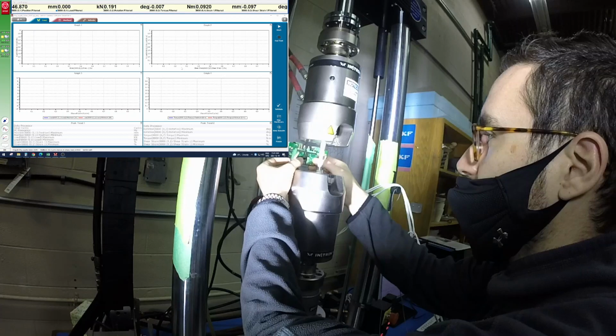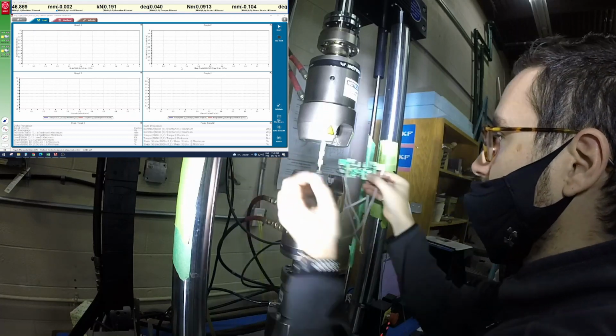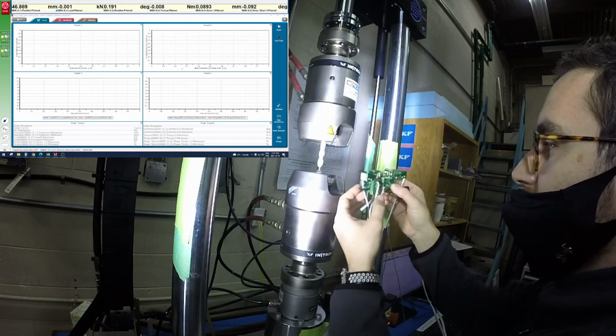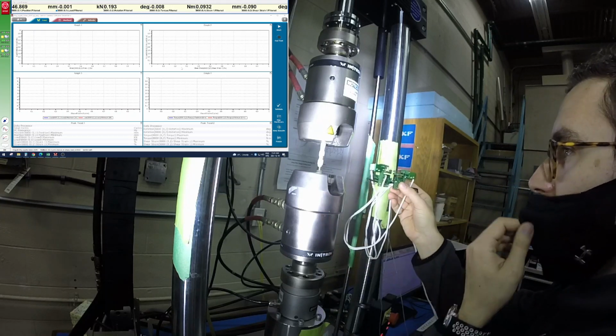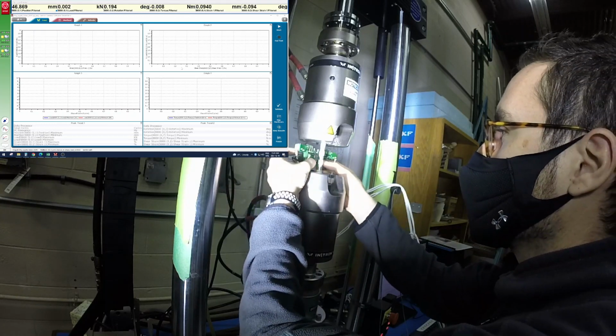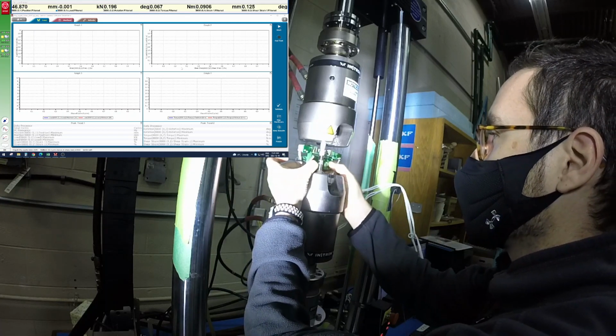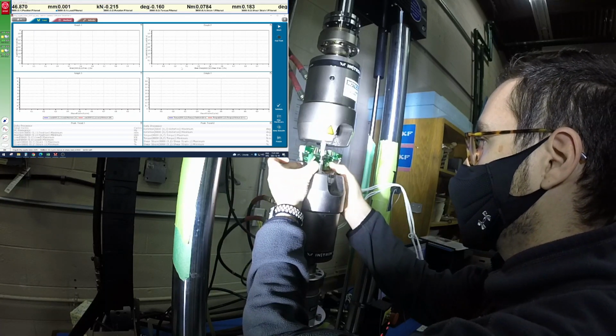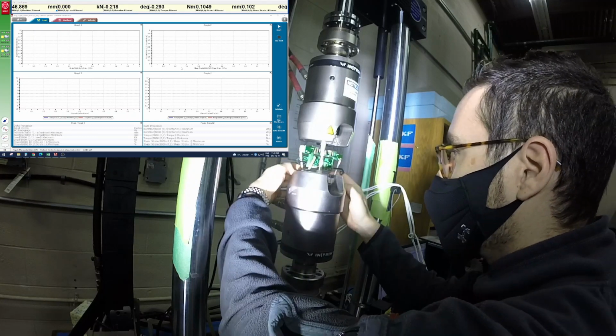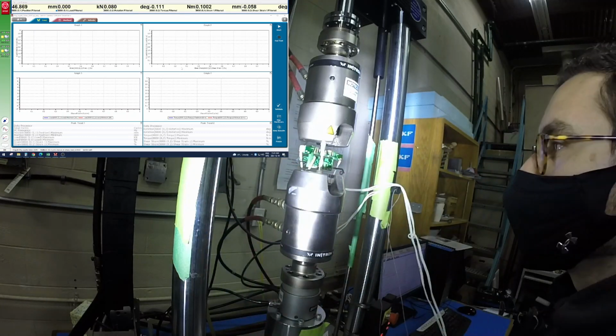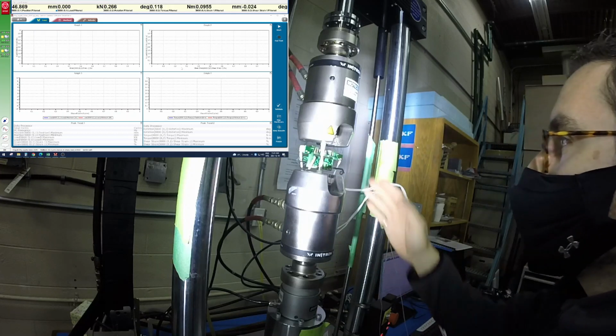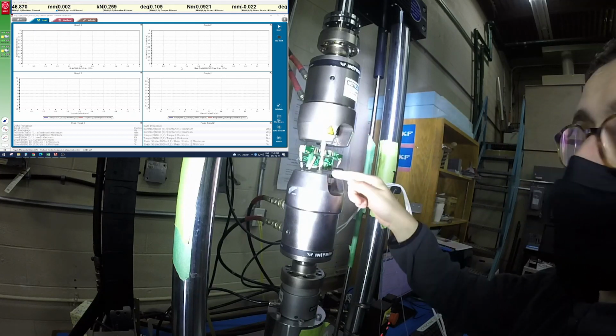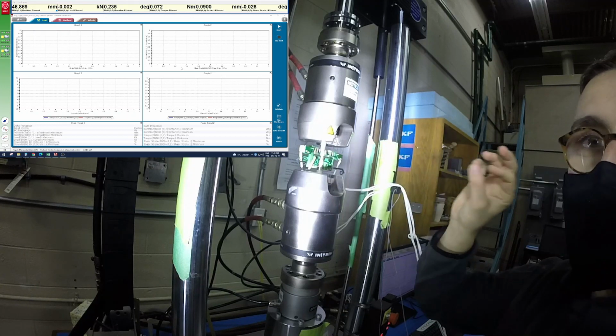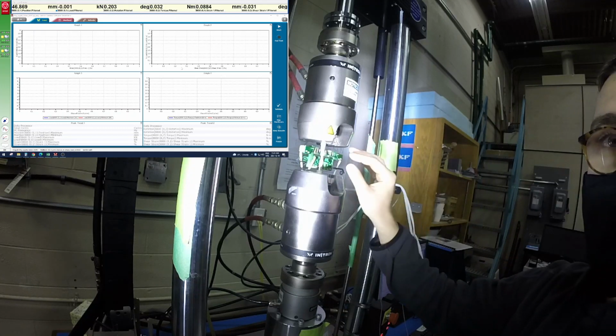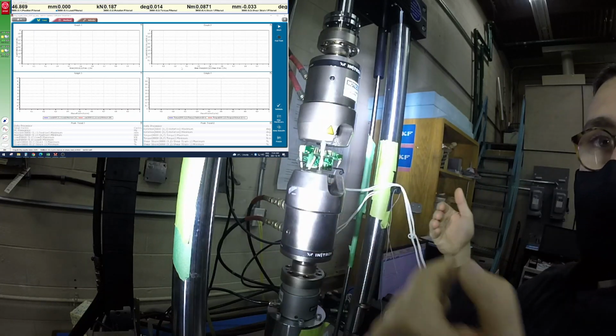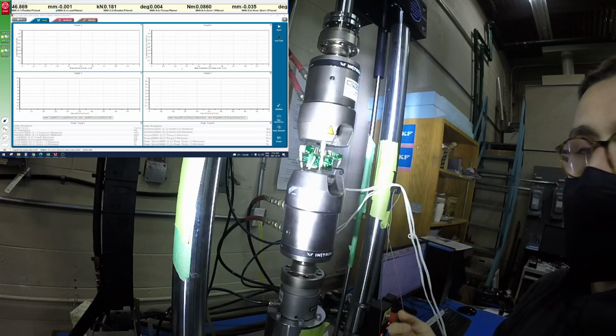So we want to take the extensometer and open it up. You can see that there's 4 pins here that are holding the extensometer rigid. So I want to still be gentle with it, but I can open it up, as you can see here, and I can apply it to the specimen so that those pins are digging into that white coating that's there. And typically we can use a laser to define the location of this, but we want it to be symmetric and concentric on the gauge, and we want this to actually be measuring at the maximum diameter of that surface.